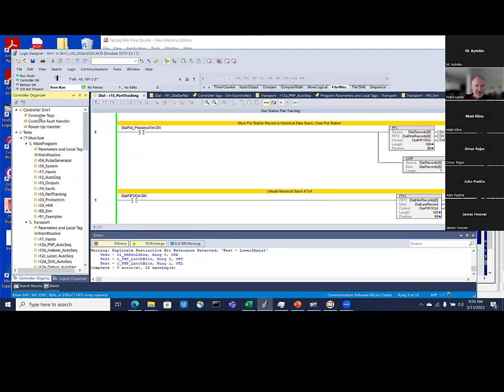It's in the local tags. Another question people sometimes have for me is, why do I put some tags in the controller tags and others in the local tags? In general, if it applies to the entire machine, like dial historical records, I put all my records of things in the main routine because some SCADA programs have a harder time drilling down into these program tags. The program tags are for things so you don't clutter up the controller tags. You could see in that big program I showed you before that had 70 different programs in it and 70 sets of local tags. I would not want to put all those tags in the controller tags. It would make it a nightmare to find anything.